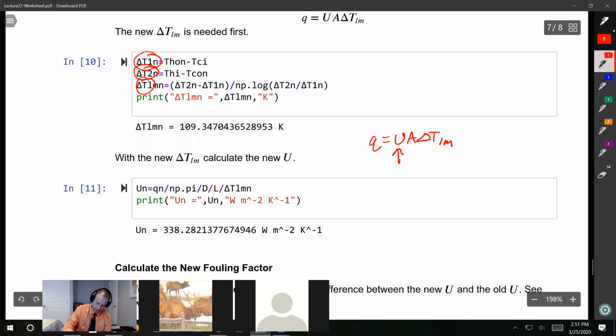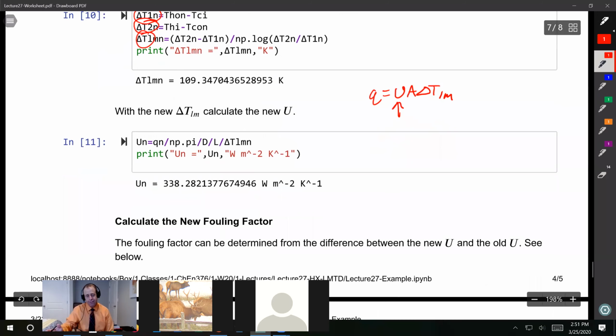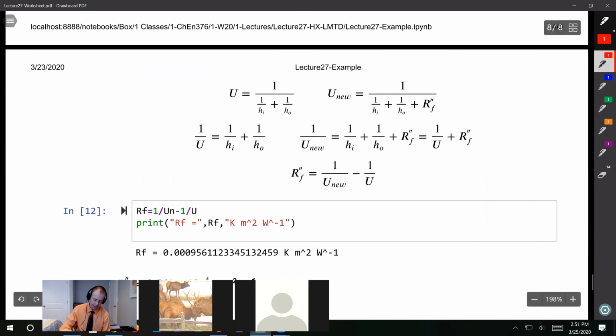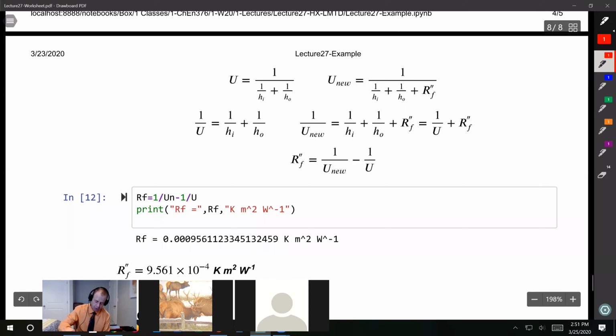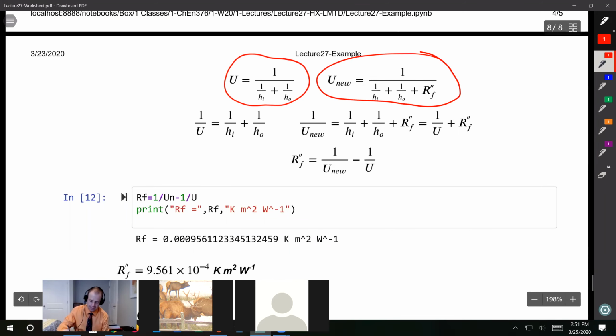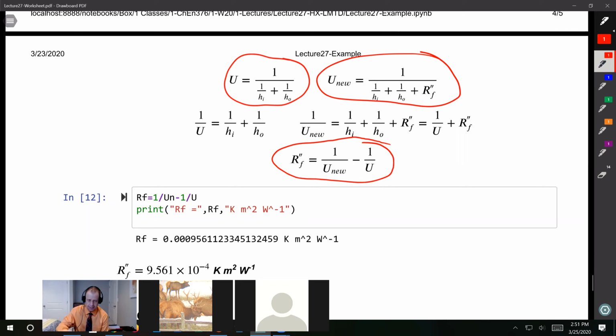Why do I want the new U? To determine my fouling factor. Look at this little mathematics here: here's what U equals without fouling, and here's what U equals with fouling. If you go through the math, you can just subtract 1 over U new minus 1 over U to get the fouling factor.